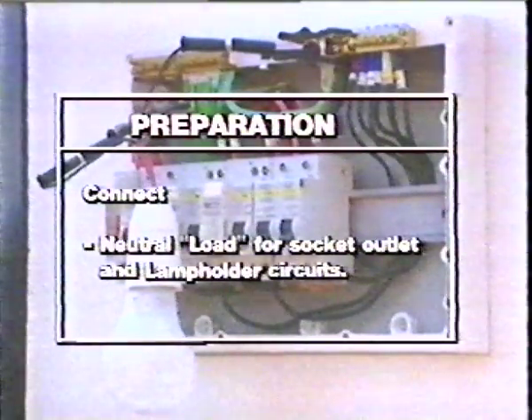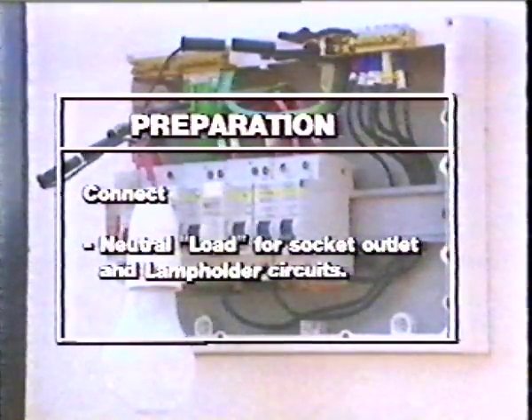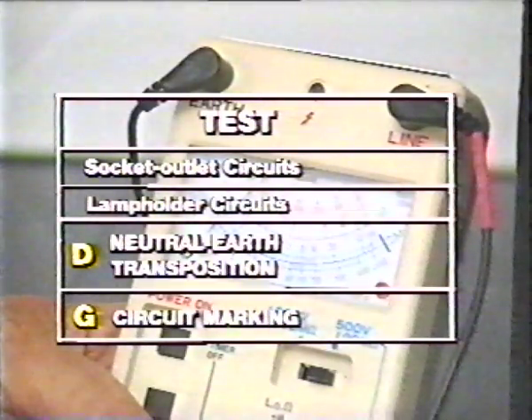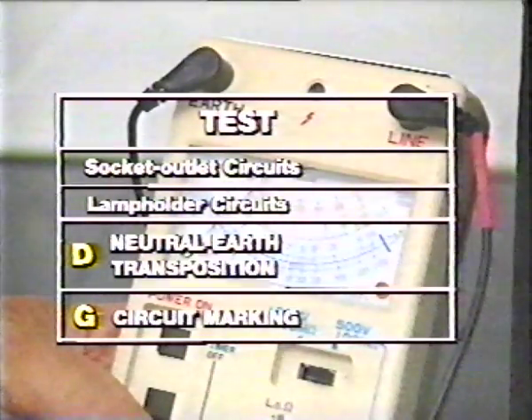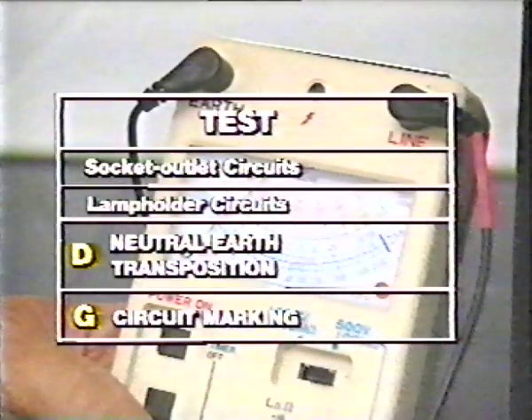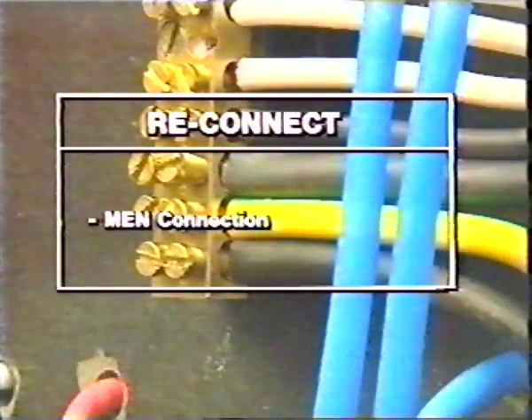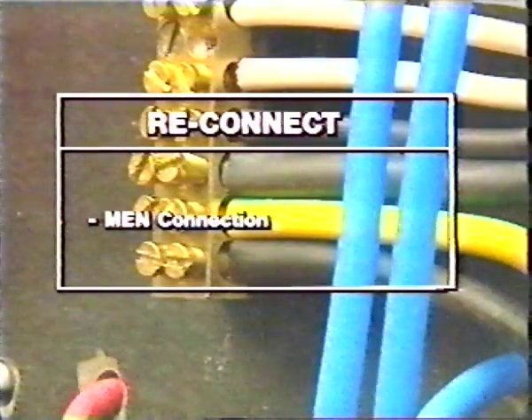Correct neutral earth connection is proved when neutral to earth indicates lamp resistance and earth to earth indicates a short circuit. Circuits consisting of lamp holders can also be tested by this method. Circuit marking, test G, is generally checked in conjunction with test D, neutral earth transposition. Now reconnect the MEN connection.